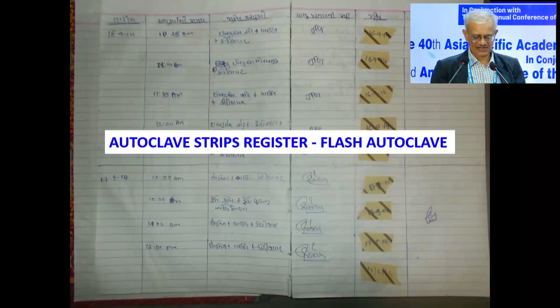Then we are using biological indicators which need to be used every week. That needs to be sent to the laboratory, and at the end of 72 hours, if no growth is seen, then we can certify that the sterilization had actually occurred. So this also needs to be reported, and a register needs to be maintained.